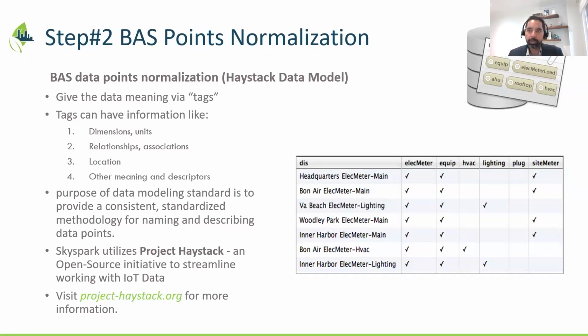So the rules are based on haystack tagging, meaning once a point is tagged, it can be used to apply the rules. For any organization, this is a one-time exercise to normalize the tags. Once it's done, you have standard rules already developed that can be applied, because your points are normalized with tags, which are taken into consideration by the rules—so you don't have to change the rules all the time. You just tag the points, and that helps you define and implement those rules.